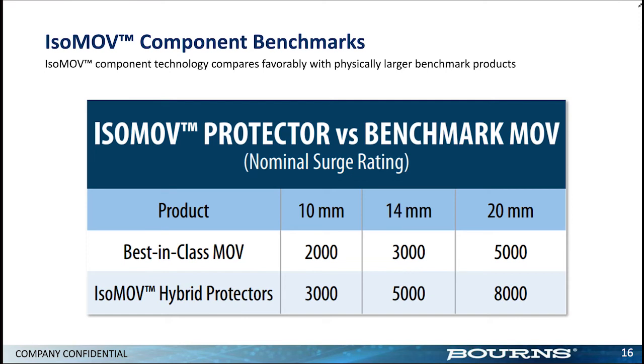So typically on some of these examples where we actually test based on the 8x20 surge waveform, and if it's a slow rise time, again, the GDT, the IsoMOV, basically have what we call the VFP. So at the higher surge, higher rise time, because the GDT is a lot slower to respond, you will see a higher peak breakdown compared to if you do slower, and the slower rise time will actually have a lower breakdown than the high rate of rise.